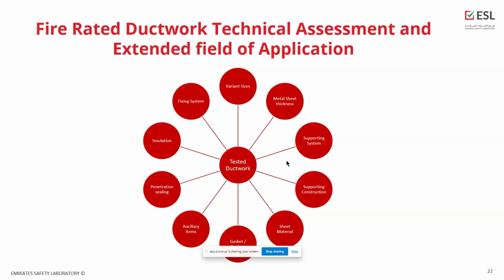Normally it will be tested with one material sheet, something like galvanized steel. You will have the options for mild steel, stainless steel, and the supporting system, because you also need various supporting system sizes to accommodate the differences in ductwork sizes, supporting construction, same as Daniel explained, the type of supporting constructions, and also the sheet metal orientation, gasket, and ancillary items, penetration seal, insulations, and also the fixing system. All this is a component of the system. All these are details of the system. They need to be assessed to see the limitations, and also assessed carefully, not to extend to something out of practice, or to limit it to something not practically applicable.